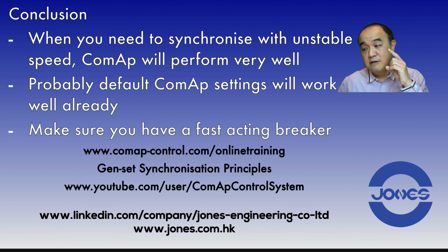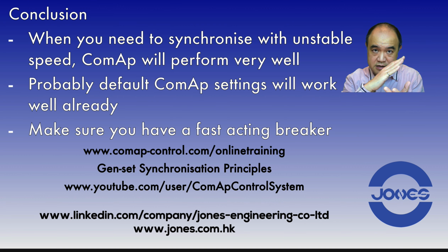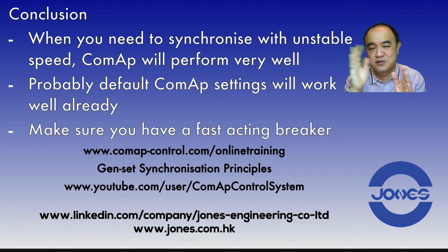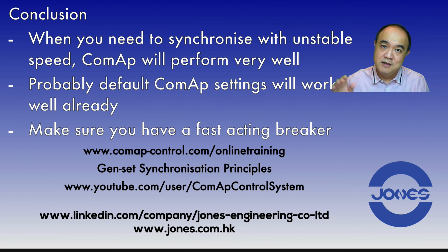Now, of course, a very important thing: make sure you have a very fast breaker. If you want to synchronize gensets, don't use a cheap slow breaker. Those days are gone. We have very fast air circuit breakers today. Take a fast breaker. When we give the command to close, it will close immediately. Then everything would work.